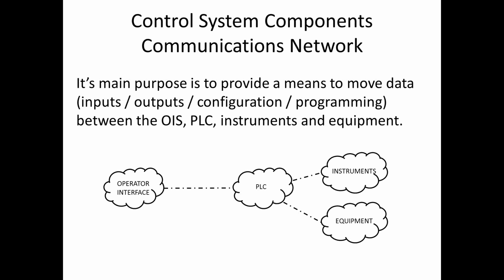So the communications network is what really ties all the equipment and instrumentation together. Its purpose is to move data between all the various components of the communications network. The instrumentation sends the signals to the PLC. The PLC looks at that and passes that information along through the operator interface so operators can observe what's going on. It will also send signals out to the equipment to control it, whether the equipment needs to speed up or slow down, whether you need to turn a mixer on or off. It will also tell you the equipment's status, how fast it's running, or whether the equipment's running at all.